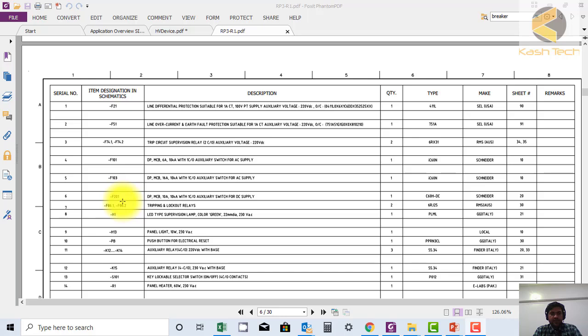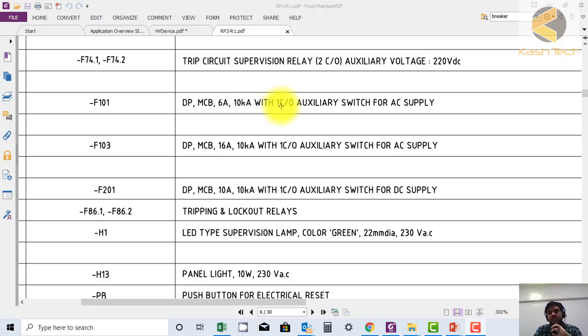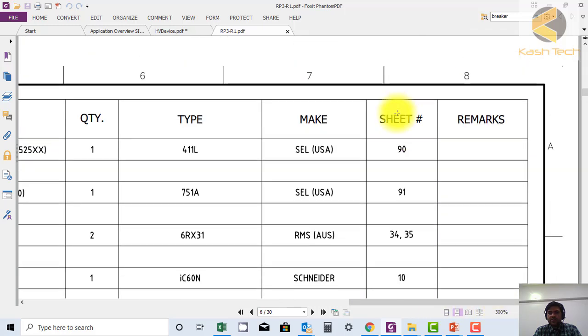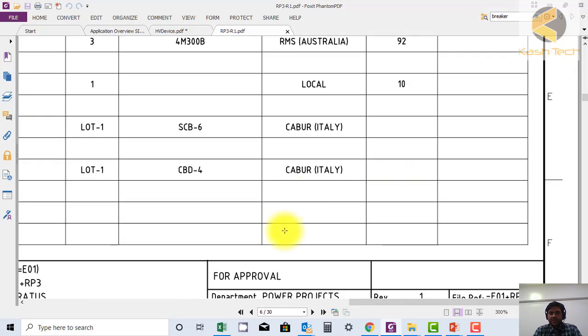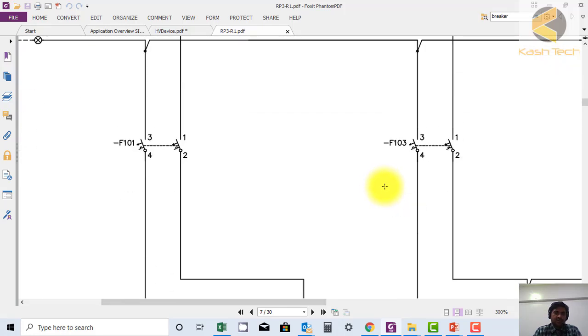Let's check how MCBs are shown in the drawing. I've opened a component list. This is F101 — you can see it is a DP distribution MCB. The rating is 6 ampere, the short circuit rating is 10 kA, it has one normally open and one normally closed contact, and an auxiliary switch for AC supply. The make is Schneider, and it is available on sheet number 10.